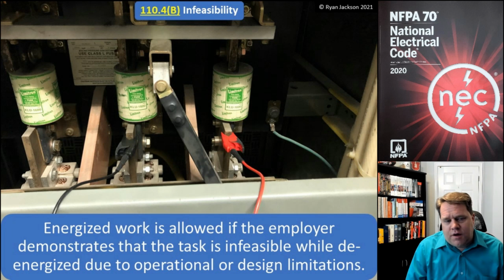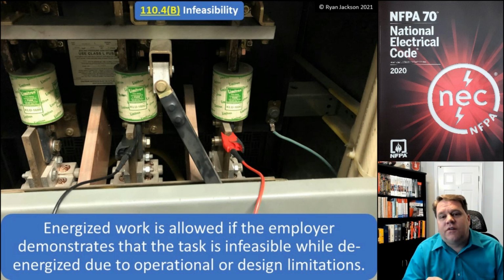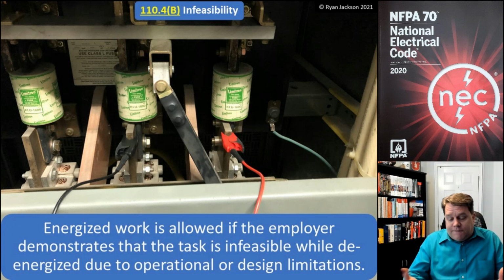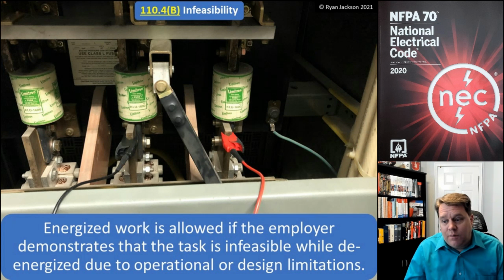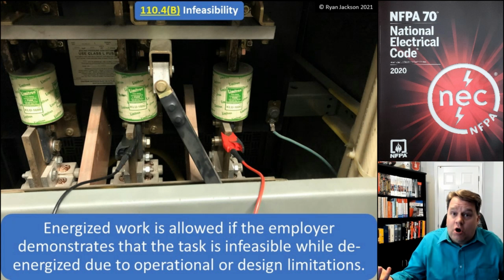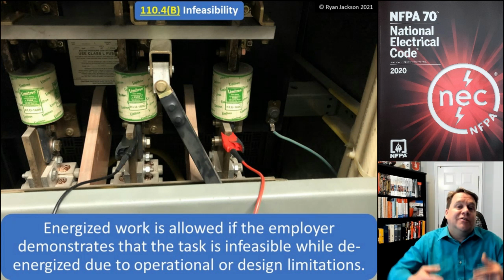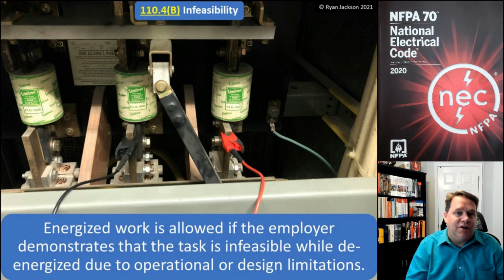Much more commonly, it is infeasibility. Energized work is allowed if the employer demonstrates that the task is not feasible while de-energized due to operational or design limitations. Okay, if I have to measure voltage on a piece of equipment, well, it has to be on. So there are certain tasks that have to be done energized.